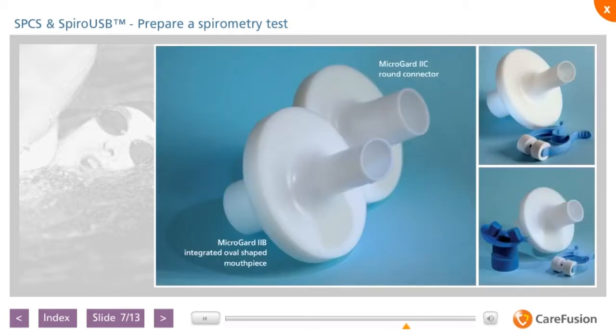MicroGard filters have a 99.99% bacterial and viral efficacy and should be used as part of spirometry hygiene and cross-contamination procedures. MicroGard filters can be connected directly to the turbine. Alternatively, if a disposable cardboard mouthpiece is used, the adapter supplied with the Micro 1 should be wiped with a disinfection cloth after each patient test. CareFusion can supply filters with a round mouthpiece or an oval one with teeth marks. Filters can be supplied on their own or with a nose clip in a single patient-use disposable set.